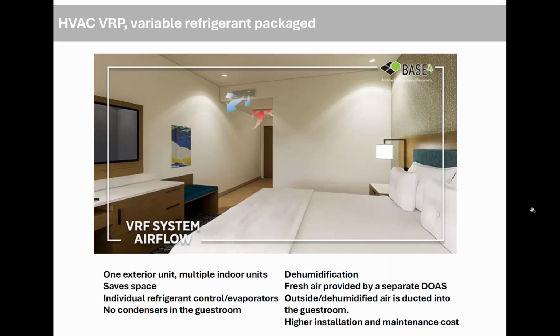And then the next one is the VRF, the variable refrigerant package system. And it's sometimes called a pancake unit. You can see it here above the entryway of the door, which is a typical place for installation in the hotel room. They'll drop the ceiling above the bathroom and the floor, or in the entry, and put that unit in like a 12-inch space there. This requires separate exterior units, and they run the refrigerant lines in and use them to heat and cool the air. That can also dehumidify.